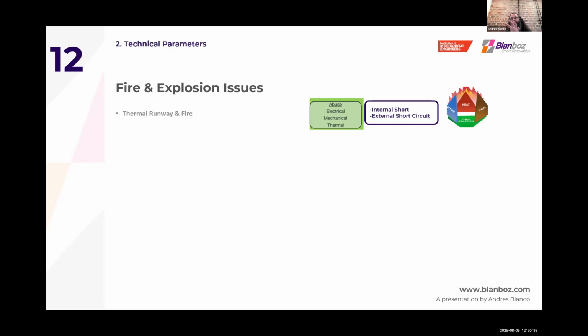What happens then is a thermal runaway event, which leads to fire. The fire and chemical reaction is a bit different from the conventional fire triangle, because you have an exothermic reaction - it creates its own heat, which is a fundamental issue for firefighters trying to put out fires in battery projects, because almost nothing will put the fire out.